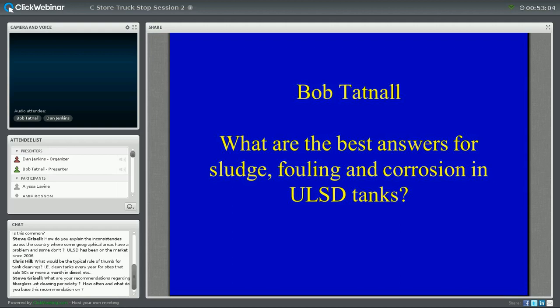One of our jobs was to go on top of one of their gasoline storage tanks, open an opening in the top of the tank, lower a bacon bomb to the bottom, pull a sample and test it. We tried to get near the center of those big tanks because they're all conical bottom with a water sump in the middle and then a 2 or 3 inch water drain line that ran out past the dike to a valve where they drew the water off periodically if they wanted to. And so we always tried to get our sample near the center of the tank.